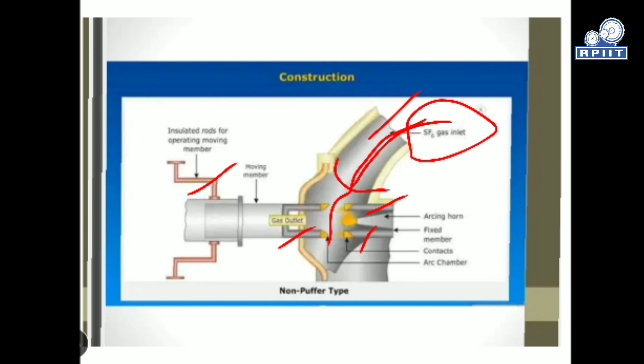During its working, sulfur hexafluoride gas is used in this circuit breaker as the arc quenching medium. As we are aware, it is an electronegative gas, so it has a strong tendency to absorb electrons. When the contacts are opened in high pressure, the flow of SF6 gas strikes the arc between them. The conducting free electrons are rapidly captured by the gas, forming relatively immovable negative ions. This is the main function of your SF6 circuit breaker.